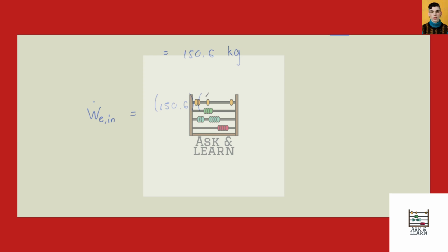And that's kg multiplied by the specific heat capacity for air, 0.718 kilojoule per kg degrees Celsius, and the change in temperature of 25 minus 5 degrees Celsius, over 11 minutes multiplied by 60 seconds. So we calculate our answer in SI units, and we get the power rating of the heater to be 3.28 kilowatts.